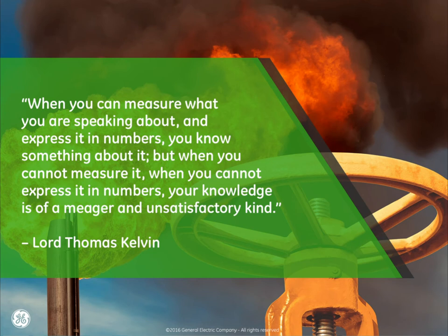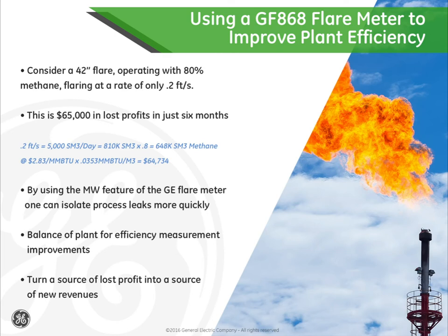We need to make measurements so that we can understand, and in so doing, we can take action. Regulations aside, without a flare measurement, we would be unable to improve processes and create a more efficient plant. Now let's look at an example. Okay, you're using a GF-868 flare meter for improving plant efficiency. Let's first consider a 42-inch flare. Let's say that flare gas is roughly 80% methane, and on average is flaring at a rate of only 0.2 feet per second, which is a pretty low rate, and on a 42-inch flare would be barely noticeable.